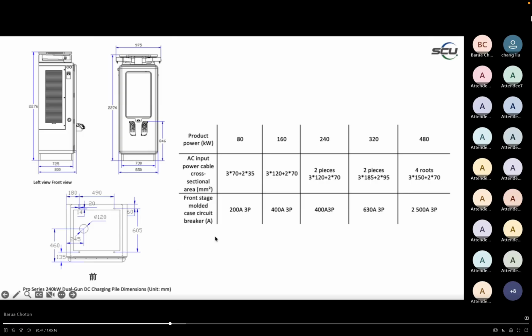For example, in an 80 kilowatt EV charger, we need 5 pieces of cable, 3 of which are ABC. We need a thicker cable, 70 square millimeters, and for the ground and neutral we need 35 square millimeters, so it's 3 plus 2. Of course we could go thicker, but cables aren't cheap, so it's good information to have so we can plan in advance.